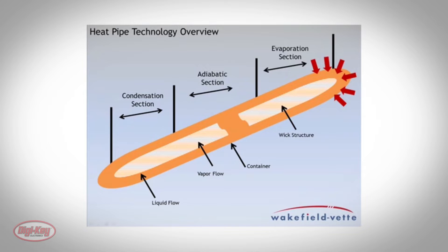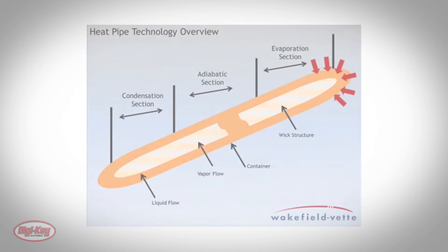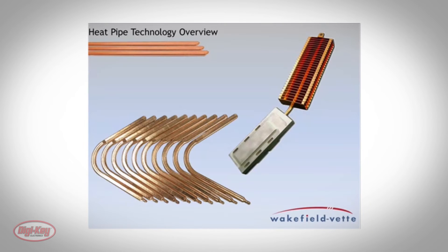The larger the diameter, the more heat that can be transported, but the longer the length, the less capable the pipe. Heat pipes can be bent and/or flattened as needed, but such modifications reduce the amount of heat that can be transported.